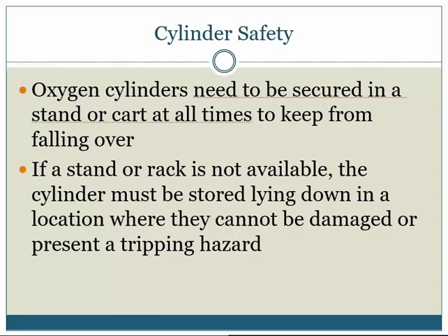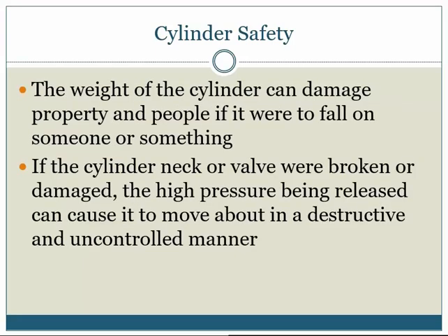They need to be secured in a stand or a cart at all times to make sure they don't fall over. If there isn't a stand or a rack available, store it lying down where they can't present themselves as a tripping hazard or something that they could easily roll off of. Again, the weight of it alone, because these things are pretty heavy, the big ones, you're not lifting up on your own. Good luck on that. That's a huge part of the respiratory curriculum, is cylinder safety and rolling them and making sure that you are supporting them and that you're not going to drop it.